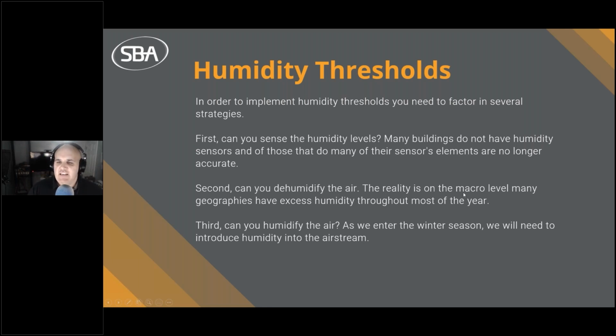The reality is, at least here in the United States, at the macro level, most of the geographies have an excess humidity problem throughout most of the year. We have very few parts of the US that have a humidification issue, meaning that the air is so dry that you have to humidify it. Most of the US, most of the year, is dealing with dehumidification, at 60, 70% relative humidity.